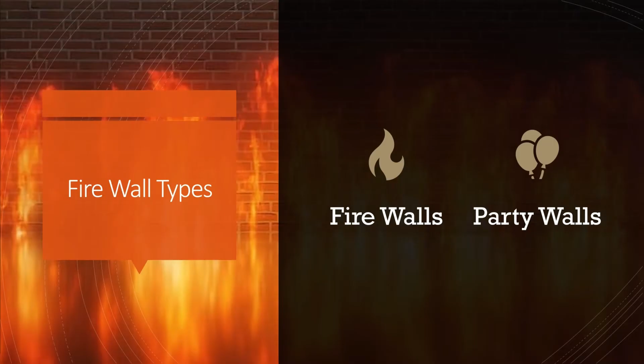This is just a picture. You'll see it later in the presentation as well, but this wall did what it was supposed to do. It doesn't look good structurally, right? But as far as what a structural engineer might want to see, for fire the wall did what it was supposed to. It remained standing, and it protected the buildings on either side of what was once a building in the middle that was on fire from catching, and again that wall remained standing. And also think of the firefighters, because that's part of the reason these need to be solid as well. If you've got firefighters attacking the fire in one building, you don't want this wall weakening and collapsing onto the firefighters and killing them. So these walls are hugely important for many reasons.